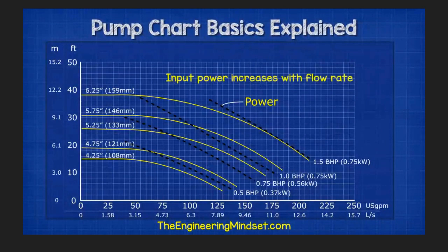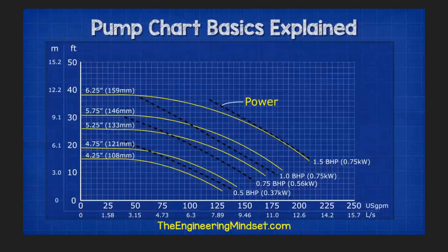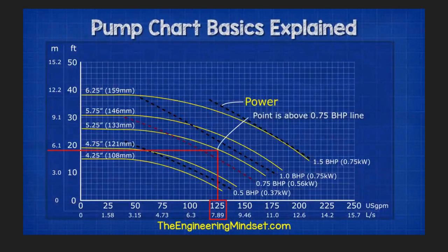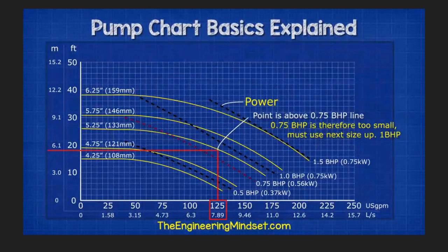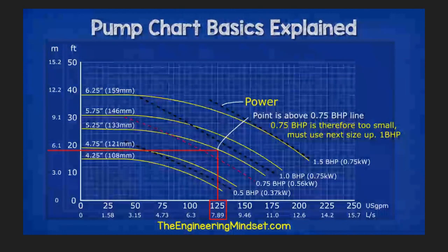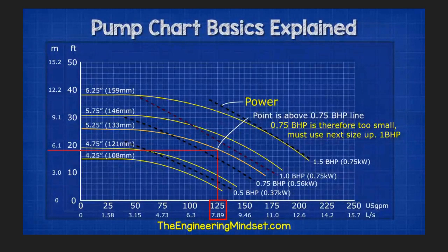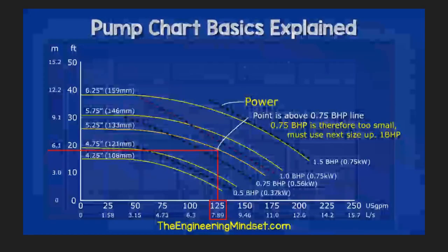As the flow rate increases, so does the power requirement. We use this chart to size our motor. For example, if we needed 125 gallons per minute with 18 feet of head, then this falls between the 0.75 and the 1 horsepower lines. Since this point is above the 0.75 line, we cannot use a motor of that rating. Therefore we will have to use a one brake horsepower motor, and the performance curve falls completely under this line, providing some safety margin if head pressure calculations are off.